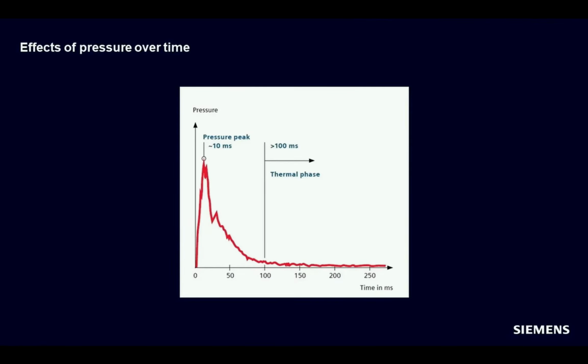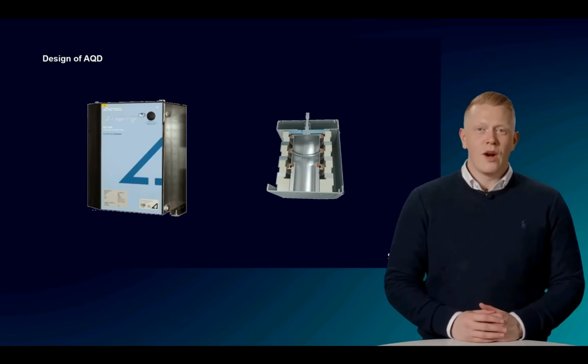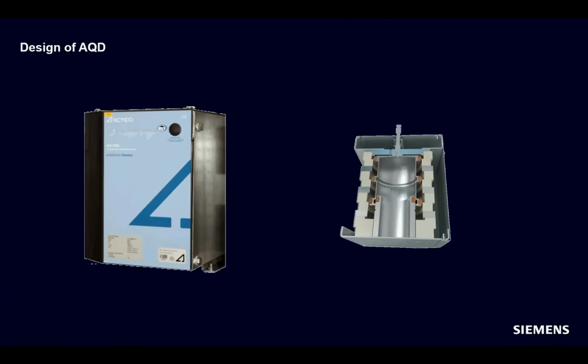How does the quenching device work? The setup is quite simple. Inside the device is a cylindrical contact which is moved extremely fast when triggered by the magnetic field of the coil and thus creates a short circuit.